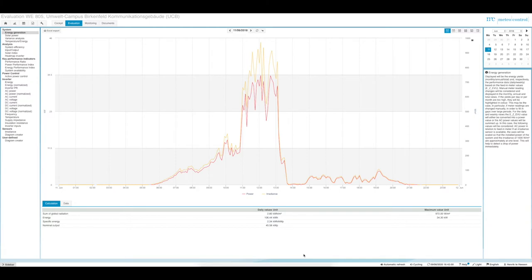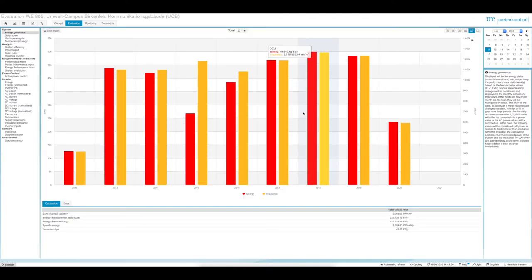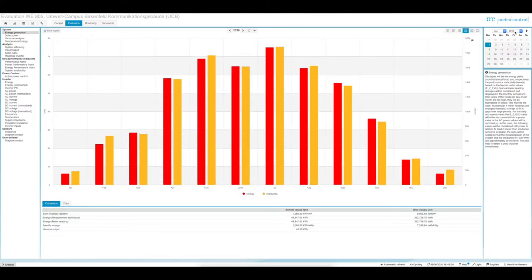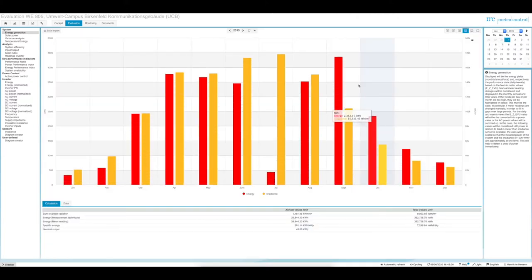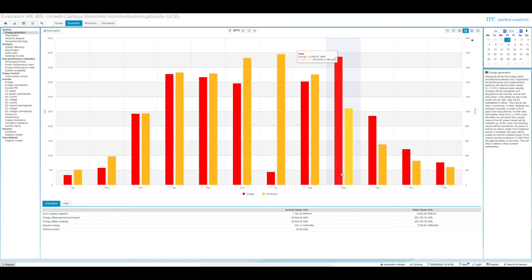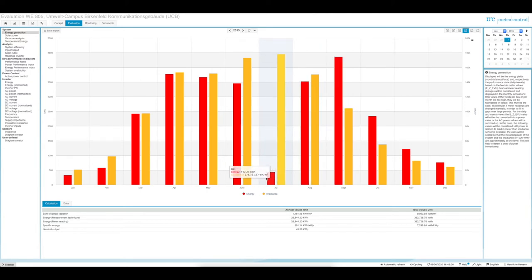In a previous video we saw there was a power generation issue in 2015. We want to look at what might be the reason why the yield production was significantly smaller in 2015. You can see the red bar is significantly smaller compared to 2016–2019. In the annual view for 2015, something happened in July — this red bar is significantly smaller — and also in September and October something appears wrong.